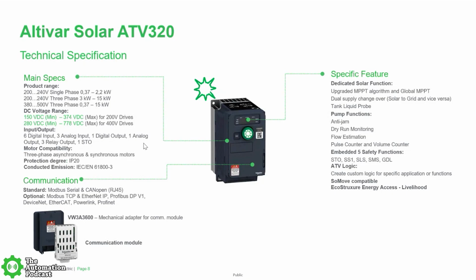So our traditional IOs that we have with our Altivar Machine are the same IOs that we have with the Altivar Solar 320. We can do synchronous and asynchronous motors, so induction and PM. It's IP20, mainly for panel build applications, and has our conducted emissions, so our EMC standards as well, and protection. Communication is here as well. The Modbus and CANopen are the standard, and our optional communication cards are here as well.